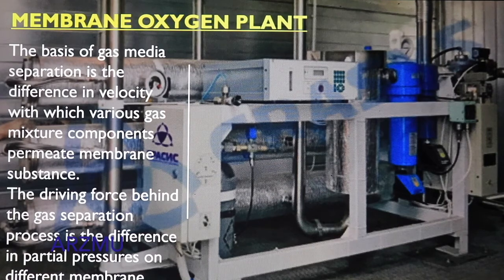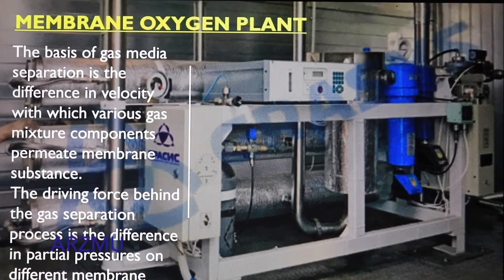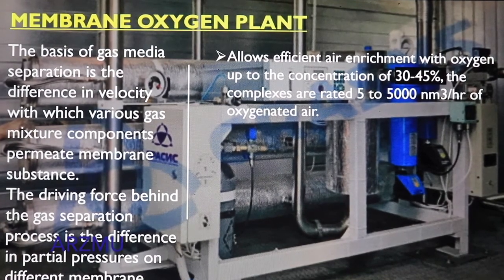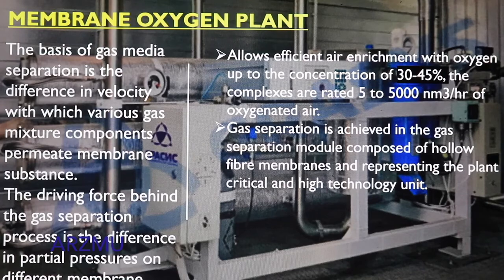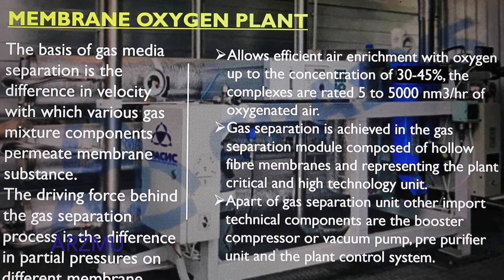Membrane oxygen plants allow efficient air enrichment with oxygen up to a concentration of 30 to 45%. The systems are rated 5 to 5000 normal cubic meters per hour of oxygenated air. Gas separation is achieved in the gas separation module composed of hollow fiber membranes, representing the plant's critical high-technology unit. Other important technical components are the booster compressor or vacuum pump, pre-purifier unit, and the plant control system.